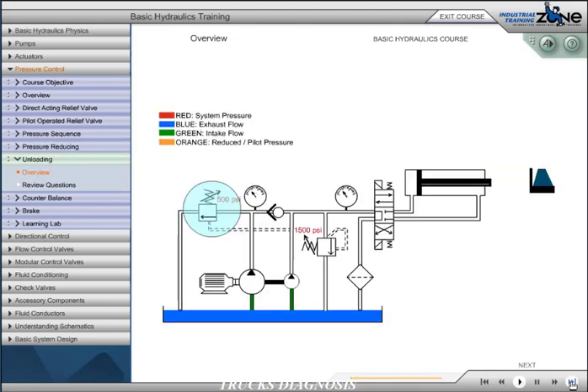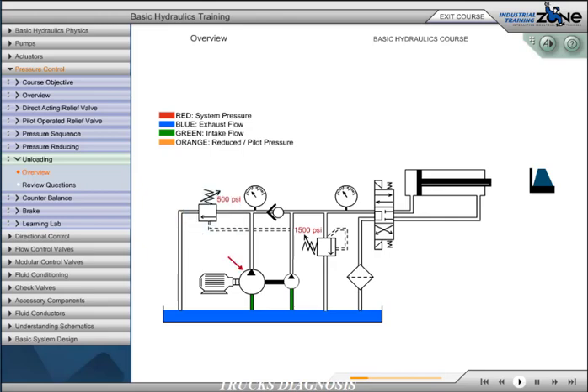An unloading valve is a remotely piloted, normally closed pressure control valve that directs flow to tank when pressure at that location reaches a predetermined level. A high-low system is a good example of an unloading valve application. This system may consist of two pumps, one being a high-volume pump and the other being a low-volume pump. As the cylinder approaches the load, the pressure requirement is low.